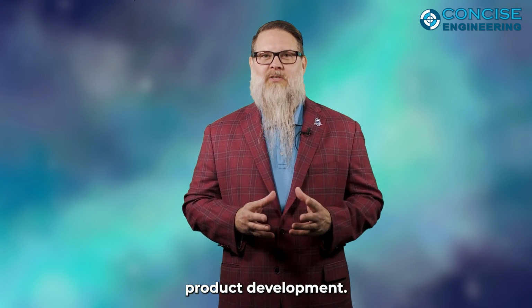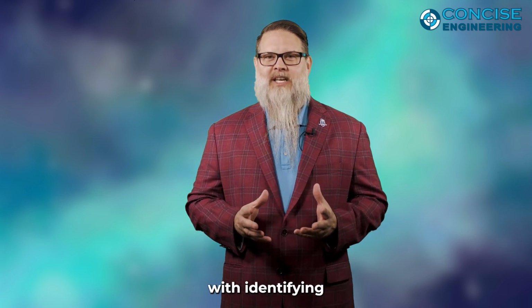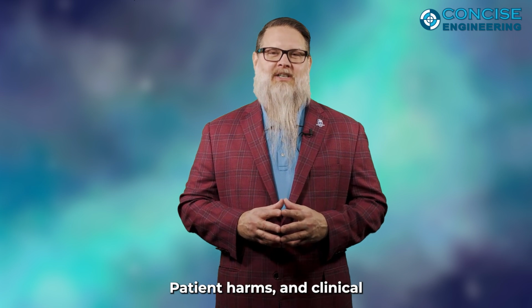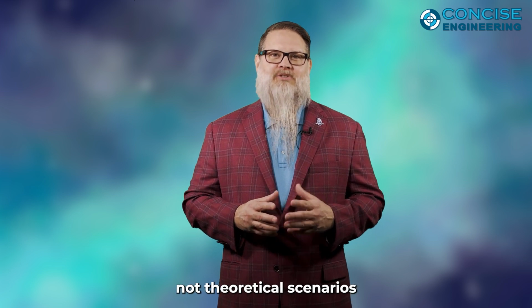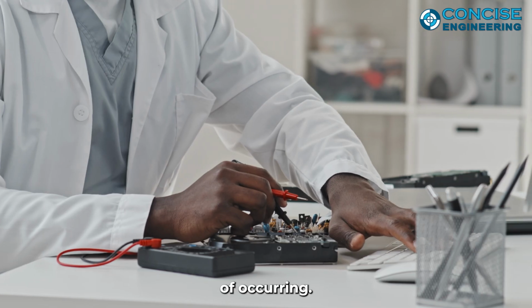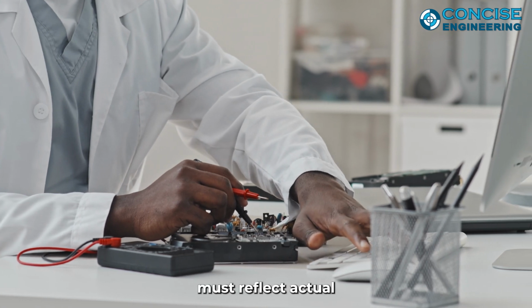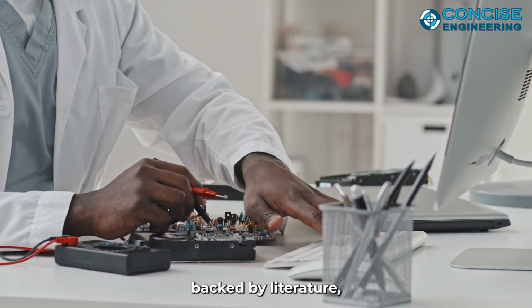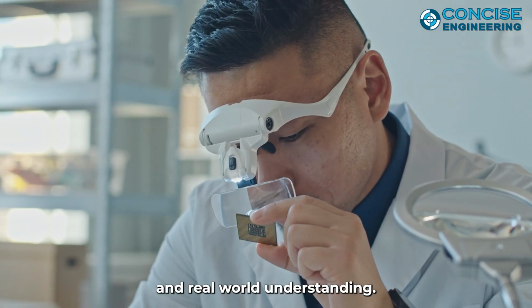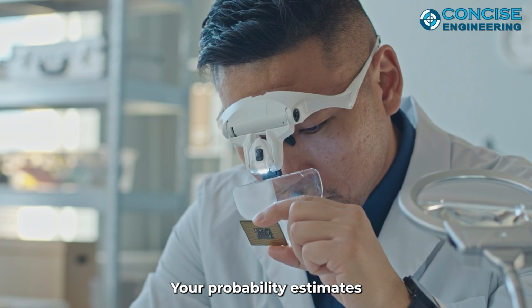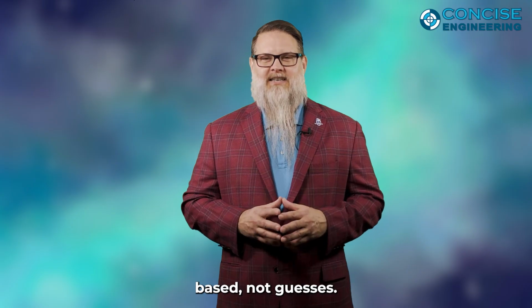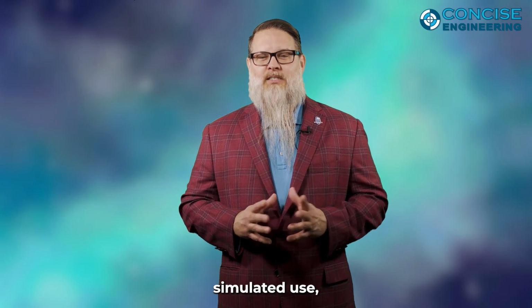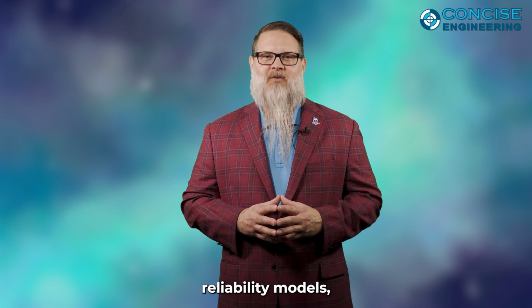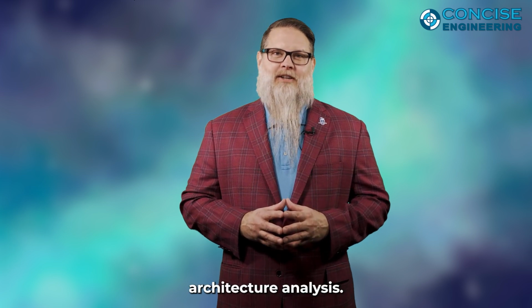smarter product development. True risk management begins with identifying real hazards, patient harms, and clinical failure modes, not theoretical scenarios that have little chance of occurring. Your severity ratings must reflect actual clinical consequences backed by literature, clinician feedback, and real-world understanding. Your probability estimates should be evidence-based, not guesses. They should come from bench testing, simulated use, historical data, reliability models, and software architecture analysis.